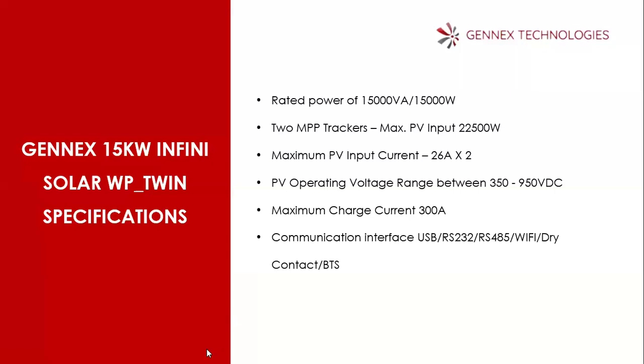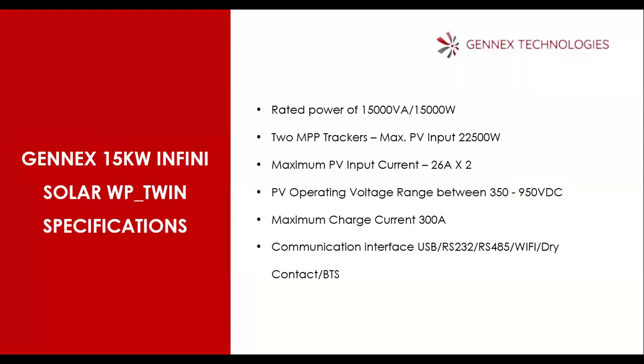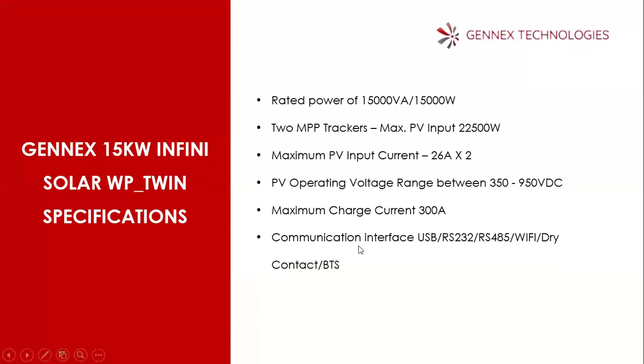The inverter also comes with a communication interface, which supports RS-232, RS-485, and dry contact as well. So you can connect it with your system to run some software and to monitor the inverter. It also has the intelligent slot, which allows you to use an SNMP card or a Modbus card. Modbus cards can be used when you want to do any on-grid or feedback to grid system and to monitor the system as well. It has the intelligent slot for that.